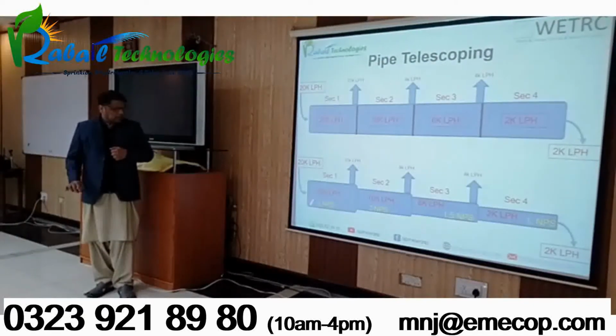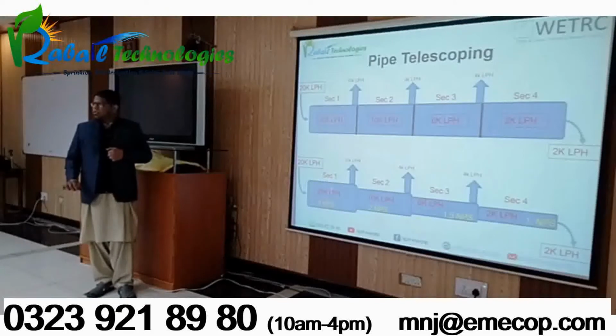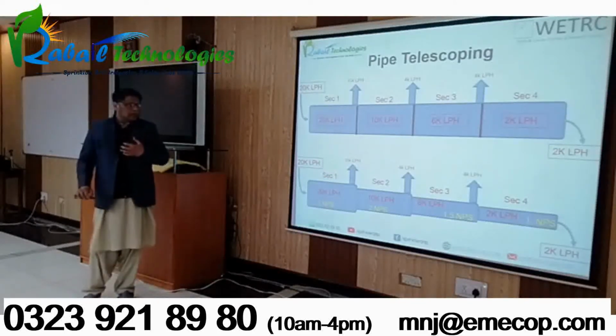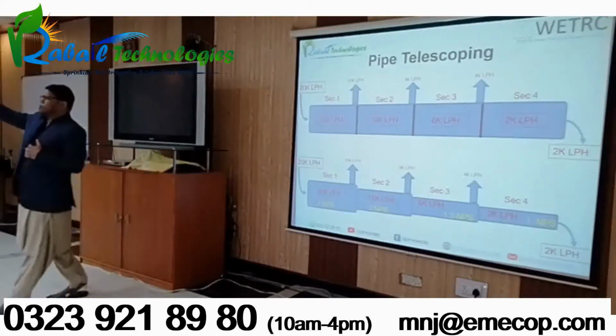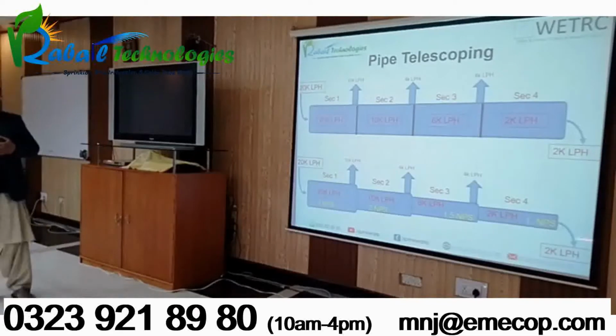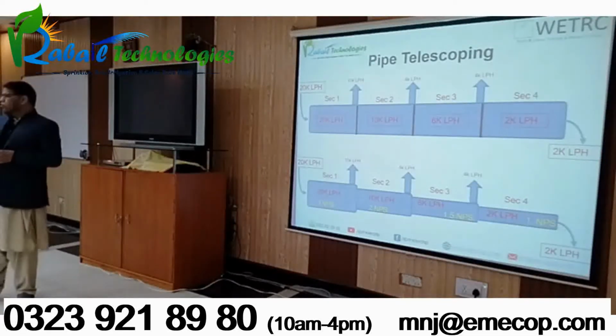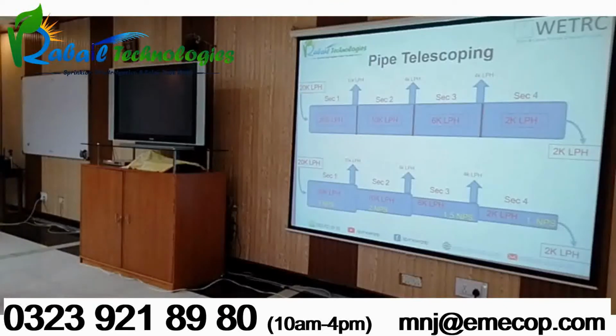So what does it mean? In section 1, as I practice, I always start from the remote point. From the farthest point I start my designing. So in section 4, the flow rate is only 2,000 liter per hour.